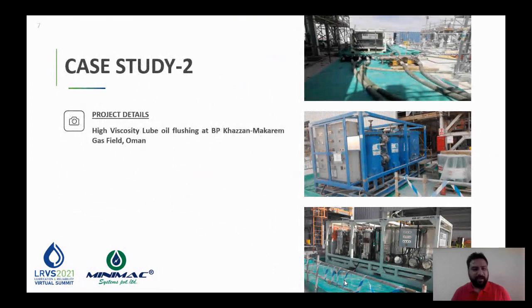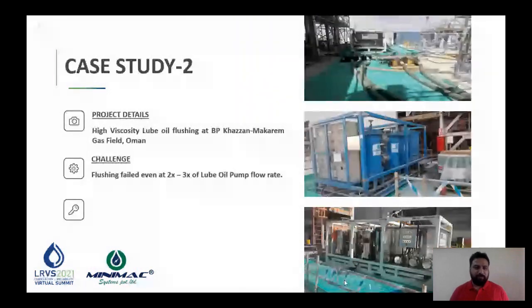The next case is a high viscosity lube oil flushing project in Oman, again for a BP Kazan. This project actually failed for flushing even though the contractor did flushing with a flow rate of 2 to 3 times the lube oil pump capacity. So even after following 2x to 3x of flushing flow rate, it didn't help because the viscosity of the fluid was much higher. Just 2x or 3x might not help you—you need to calculate the flow rate using the turbulence Reynolds number formula.